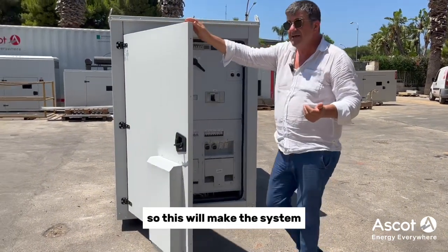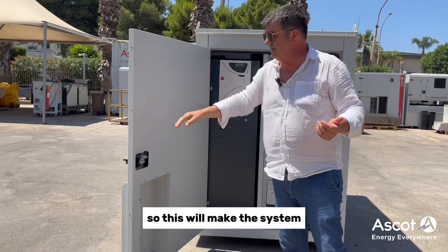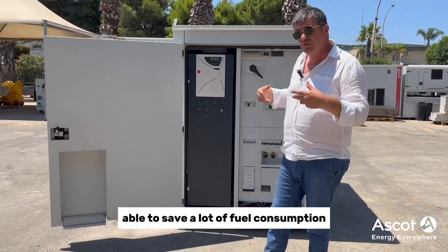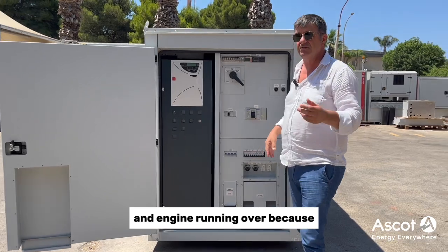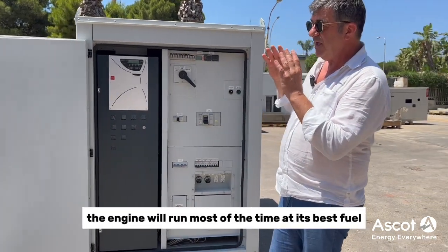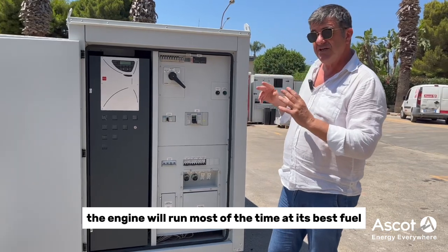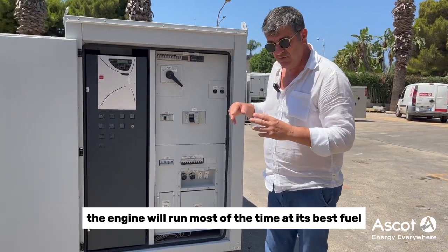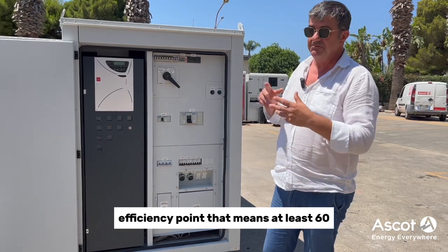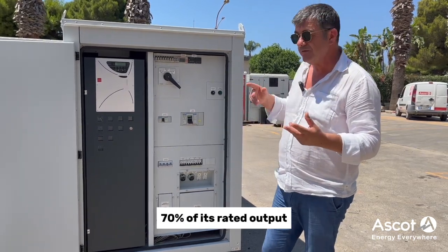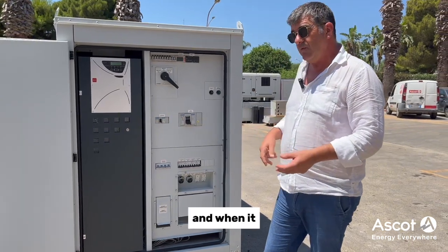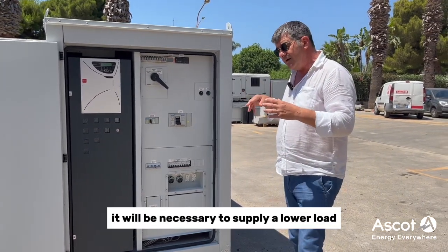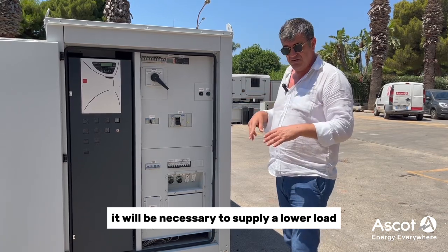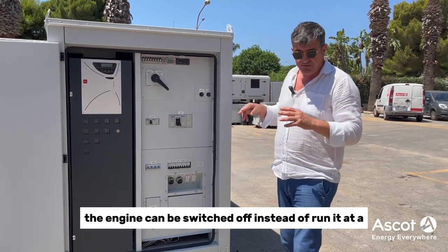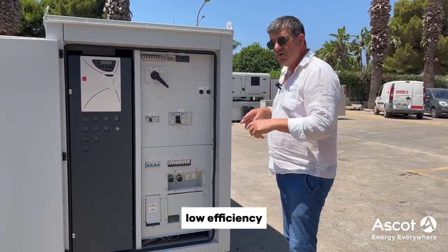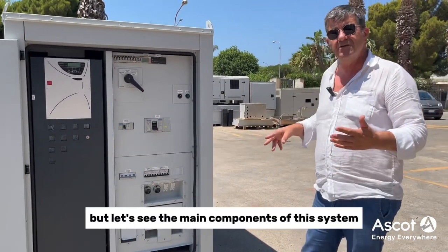So this will make the system able to save a lot of fuel consumption and engine running hours, because the engine will run most of the time at its best fuel efficiency point. That means at least 60-70% of its rated output. And when it is necessary to supply a lower load, the engine can be switched off instead of run at a low efficiency. But let's see the main components of this system.